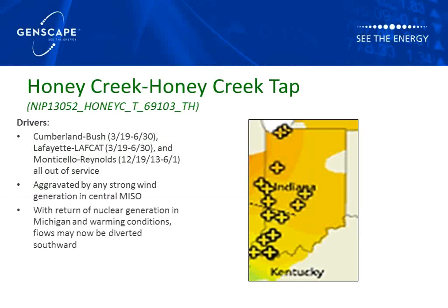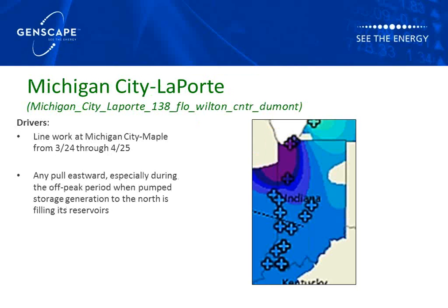So this first constraint here is a pretty familiar area right around Lafayette, Indiana. We're looking at that Honey Creek tap constraint. The drivers with this one are pretty similar, and as you can see, most of these outages have already begun. But we're seeing a switch from the Monticello East Winnemac constraint that's been appearing recently. As Lauren mentioned, that was one of the top constraints for the winter, and I know it was posting today. But really the change coming into this Honey Creek tap is we're counting on some of those nuclear units being back in Michigan, as well as some other generation to the north of that constraint coming back online. So you see less of those flows going south-north, and you get a little bit more of this Honey Creek tap congestion, which is actually a little bullish on Indy Hub.